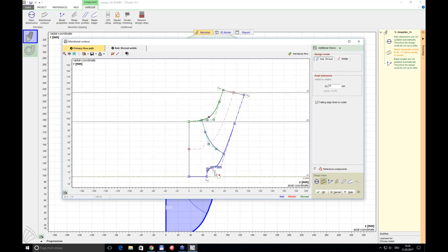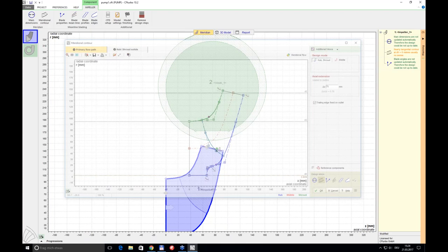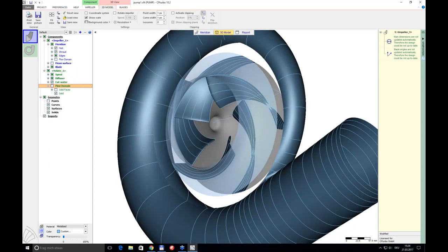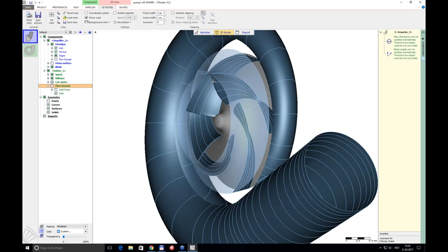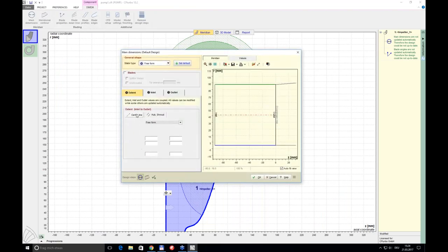With the spinner angle defined, going back to the 3D model I now have a spinner. I place an axial inlet pipe in front of the complete stage, with a length of 200 mm. I can jump between design steps using the icons instead of pressing OK, and choose from the meridional view. I make hub and shroud straight, and that's it.